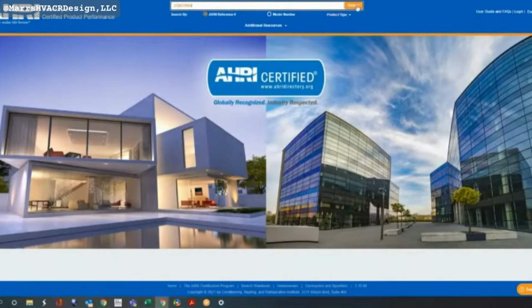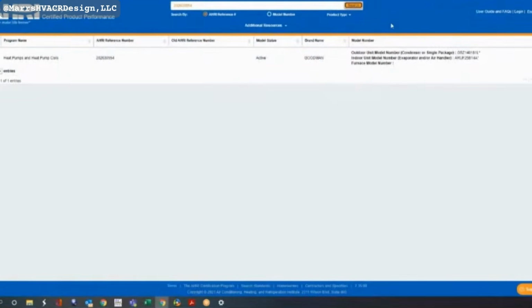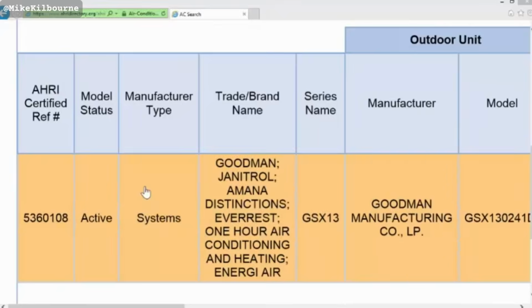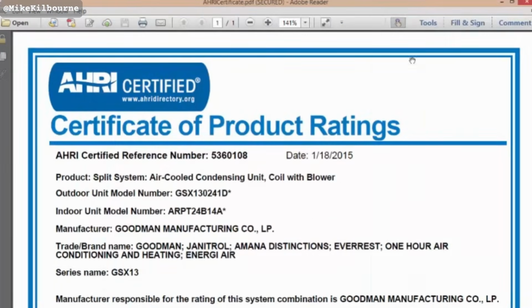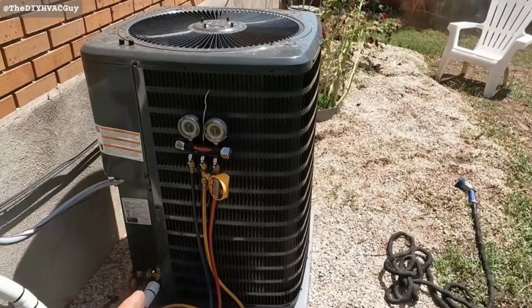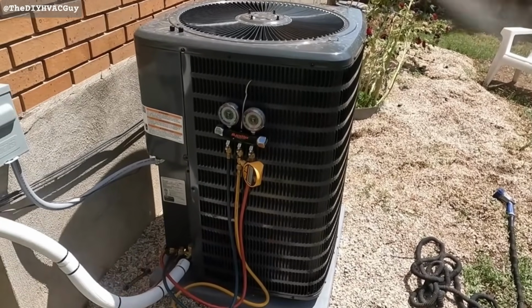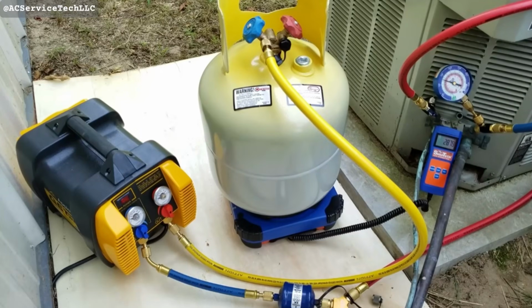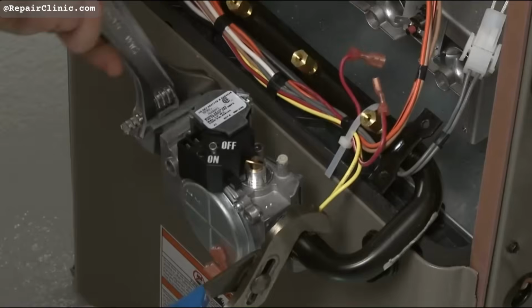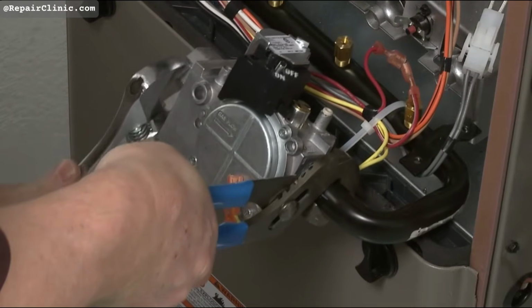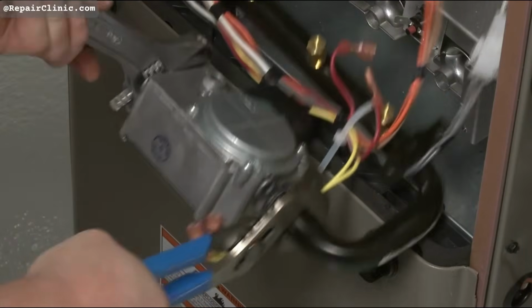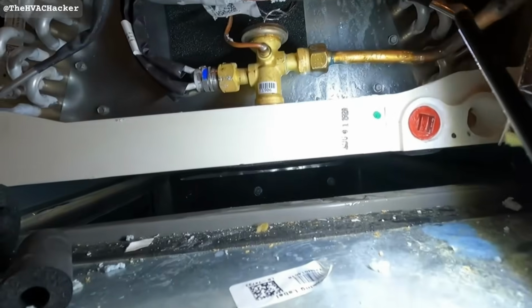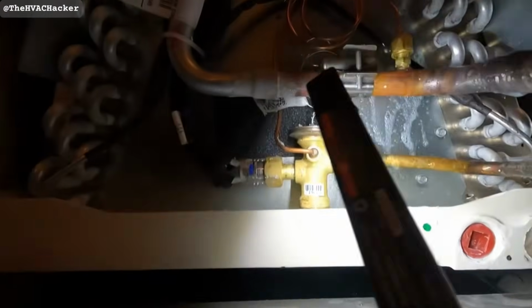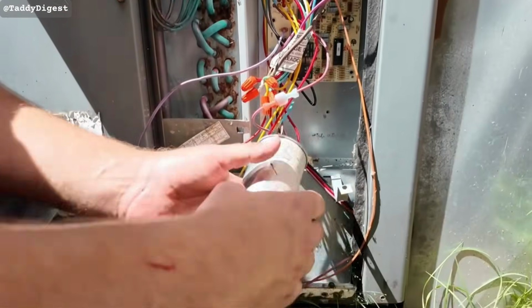Back to it. Strain source number 5 is cycling. Every time your compressor starts, it draws a brief inrush current that can be 5 to 7 times the running current. That's the strain spike. Reduce the number of starts per day, you reduce total lifetime strain on the compressor. A typical residential compressor is rated for somewhere in the range of 100,000 starts over its service life. At 10 starts per day, average for an oversized system, that's about 27 years of starts. At 6 starts per day, average for a properly sized system, that's 45 years. Same compressor, different cycling load.